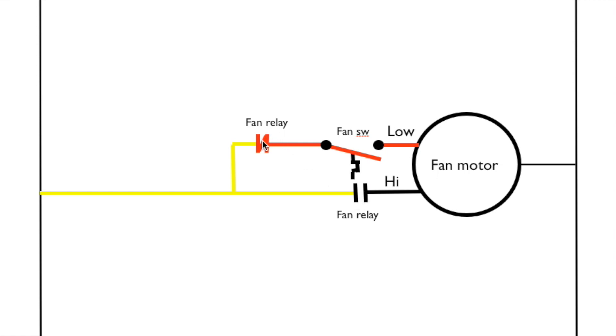Now you can see that if this high speed contact was closed, then this one would open—it's an either/or. So we cannot pass power through here even if you had a warm heat exchanger and this was closed; this will be open so only the high speed can be energized. And of course that's true the opposite—when it's in normal position, only the low speed can be energized. I hope this makes sense.